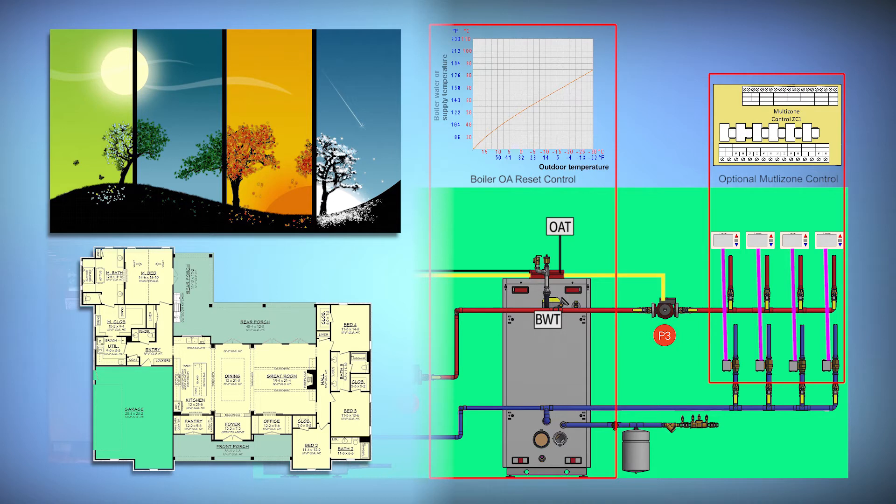This means it is not always necessary to hook up the thermostats or the multi-zone control to the boiler to turn it on and off. The boiler using its outdoor reset control will maintain the right boiler water temperature for the load in the system. When a zone calls the water will be available at the correct temperature immediately. This reduces swing in room temperature making a more comfortable environment.